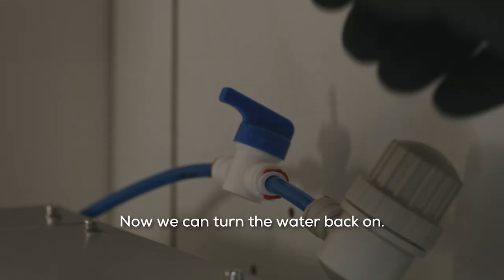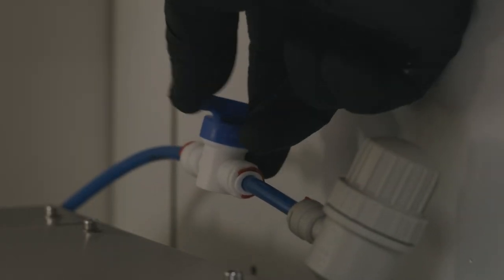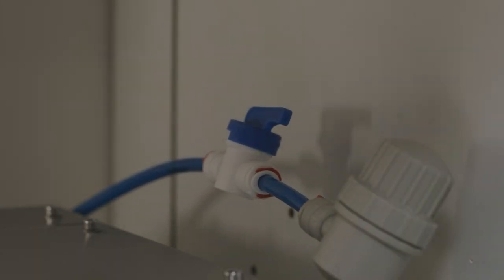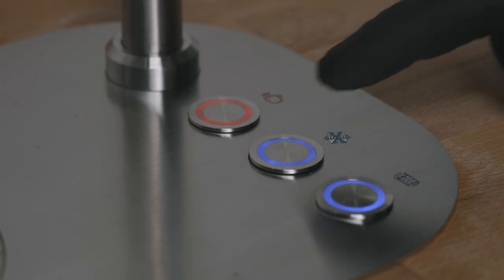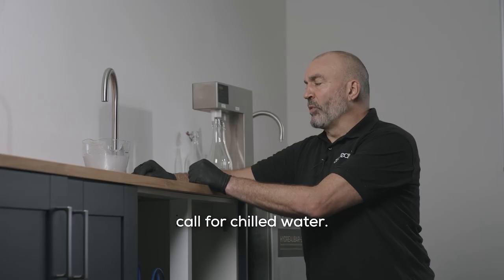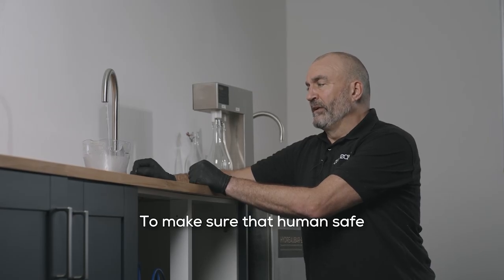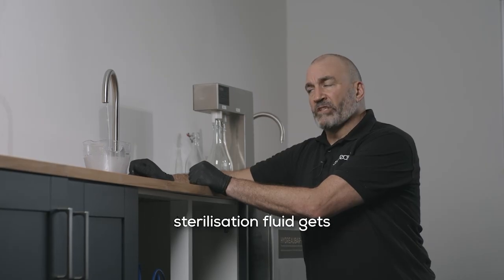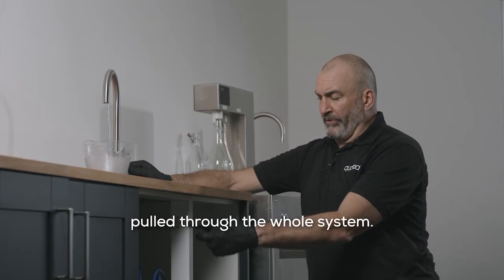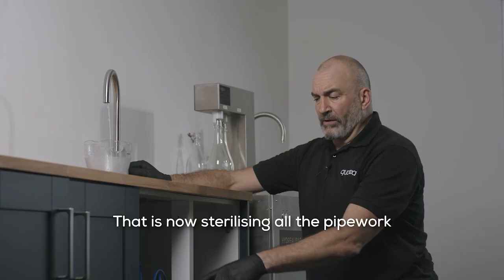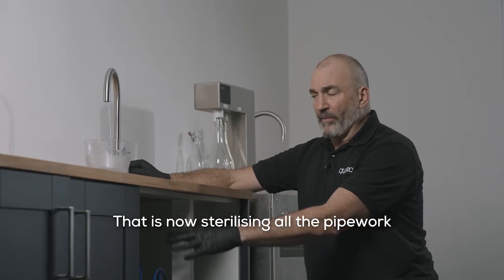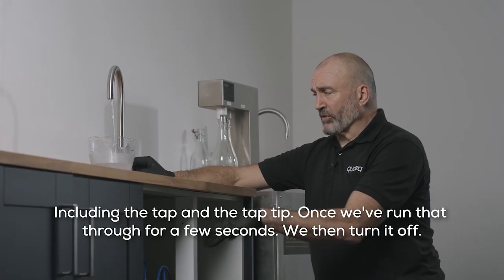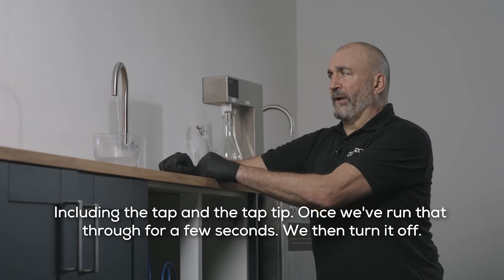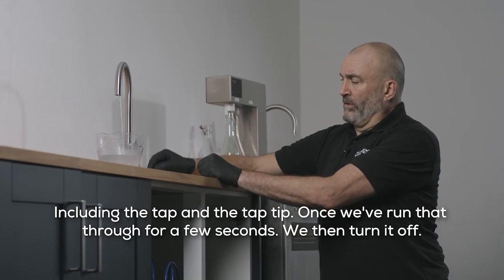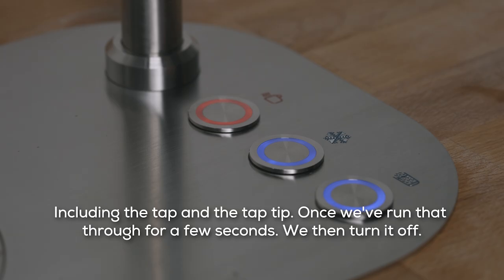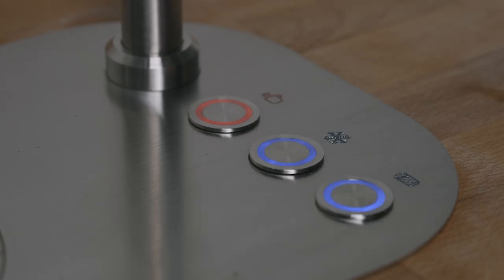Now we can turn the water back on. So we're just going to call for chilled water to make sure that human safe sterilisation fluid gets pulled through the whole system. That is now sterilising all the pipework, tank in the whole system, including the tap and the tap tip. Once we've run that through for a few seconds, we'll then turn it off.